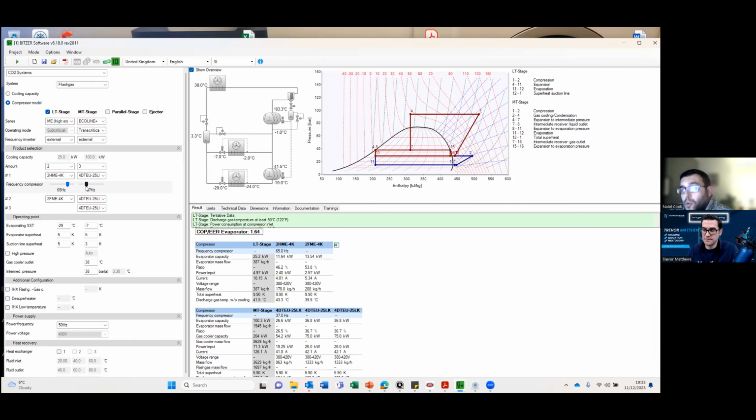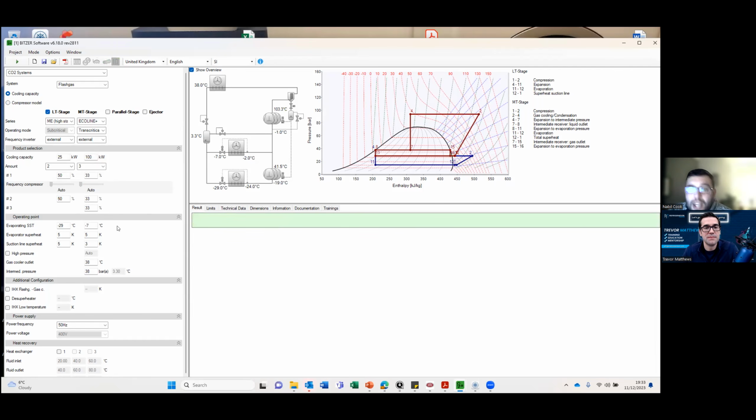But that's an enormous waste of a lead compressor at design conditions. Yeah. In real life, that thing will hardly ever run. And the design COP has come down even more. Yep. So what Bitzer's automatic selection suggested, for me, was the best of those three options. Yeah, awesome.